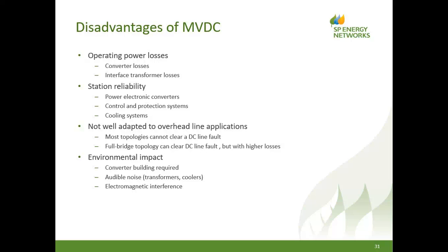The benefit, of course, would be that the losses in the AC cable would be reduced because we don't have skin effects in DC, so we can make use of all of the cross-section area of the conductors. So the transmission losses would be lower, but the station losses would be higher. We must consider station reliability. Again, we've inserted power electronic converters into the system. We have a control and protection system. We have a cooling system. So in the operational phase of the project, we'll assess the reliability of this technology. Does it achieve high reliability, high availability of energy transfer, or is it wanting in some way?